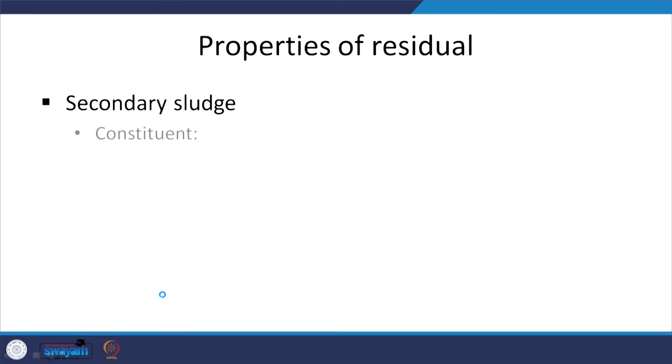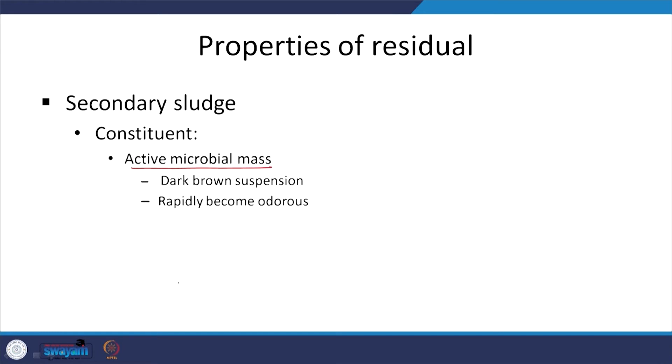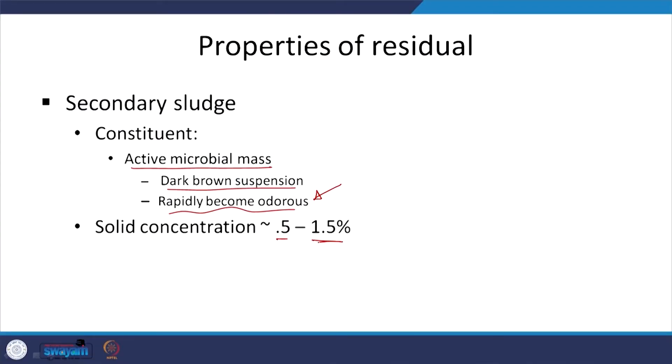Secondary sludge or from the activated sludge — what is it mostly made of? It consists of microbial mass or microbes. Typically dark brown, it is organic matter cells. These microbes will die without access to waste and oxygen, and then these dead microbes, which are organic matter, will be degraded by other kinds of microbes. That will rapidly become odorous during anaerobic conditions. Solids concentration is 0.5 to 1.5 percent, and suspended solids as expected have considerable organic or biodegradable content.